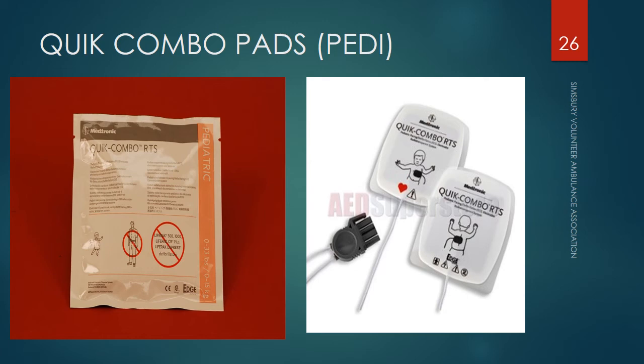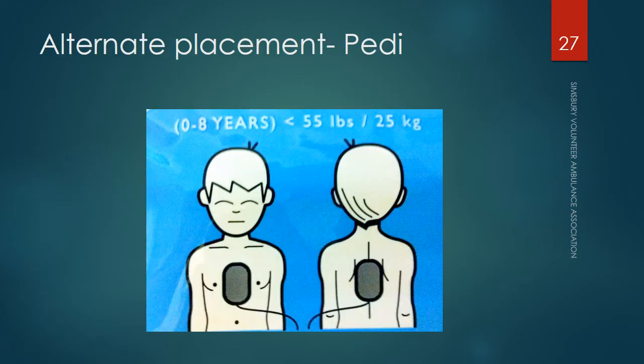You cannot cut adult pads to make them the right size for pediatric patients. You can't alter the pads in any way, shape, or form. So don't ever cut the pads. The big thing about applying pads is you want to make sure there is at least a 1-inch gap between each pad. You don't want the pads touching each other or overlapping each other, and you want to make sure there's a gap between the pads.